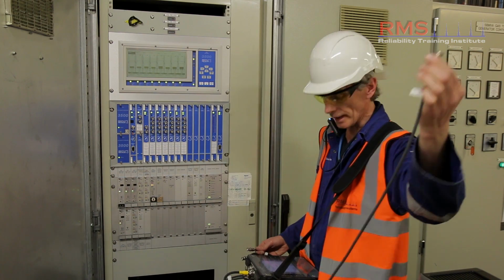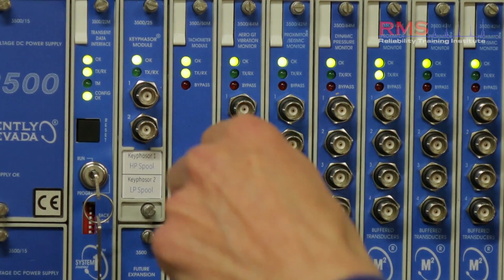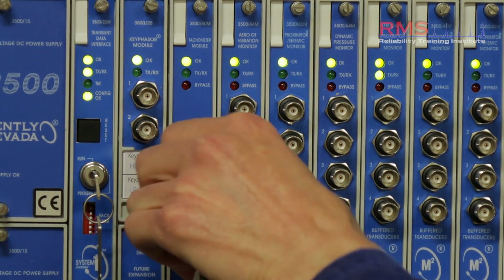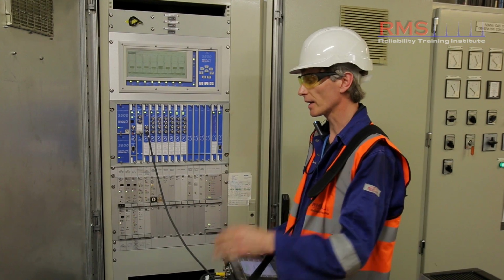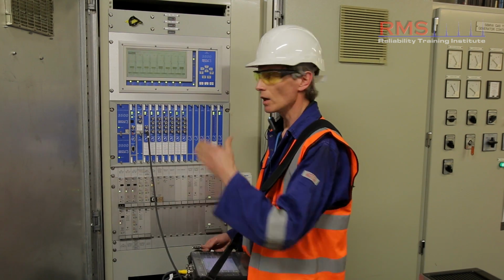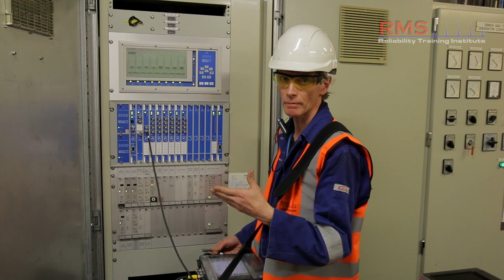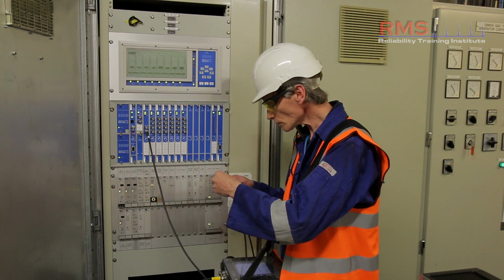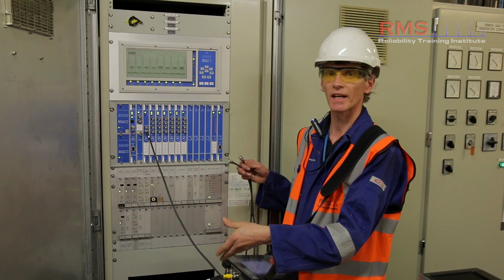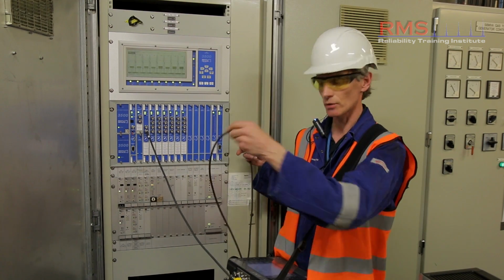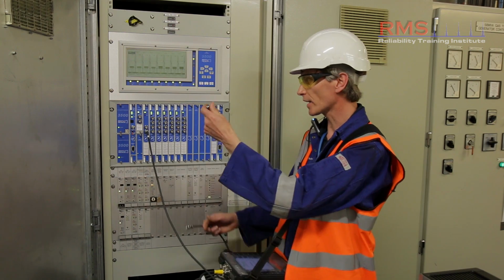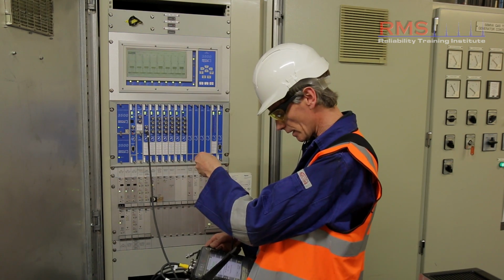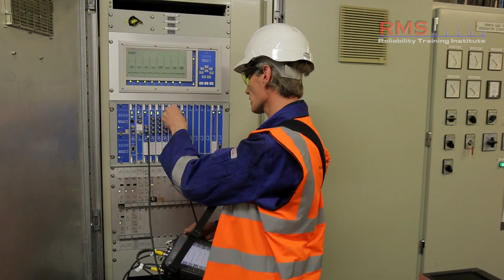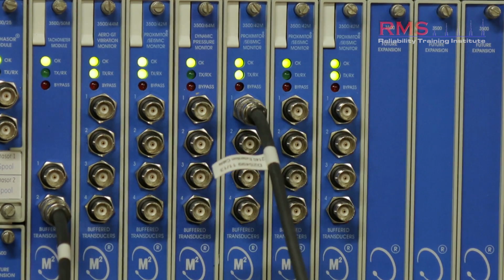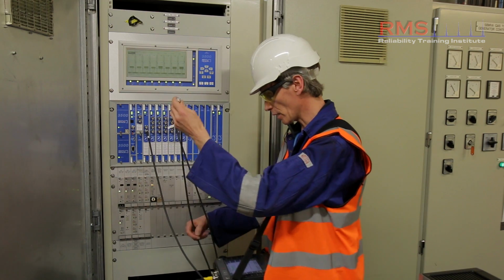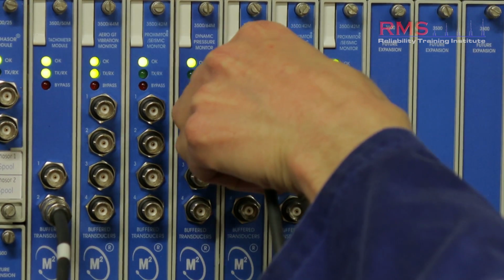So first off, I've got a speed reference signal. So I've got a Keyphasor channel. That's where my speed signal comes from, and that's a reference. It's a good datum point that I can use as a trigger and understand point by point how the motion of the system might be, but maybe that's something for another time. I have 4 channels of capability, but I'm going to plug 2 dynamic channels in. The first being the X channel, channel A. So I'm just looking on my data collector here to get the right position. 16X, that's channel A. That's good to go. And then my Y probe, proximity probe again, is on channel B. So just plug those in.